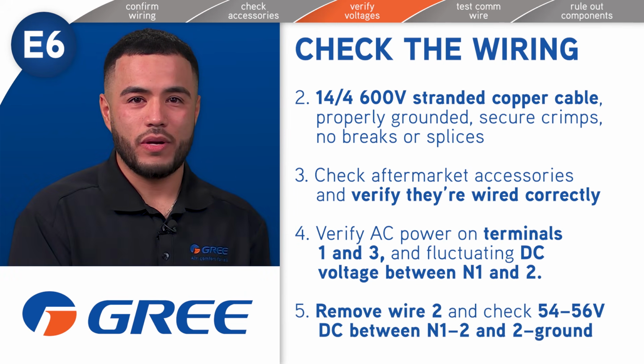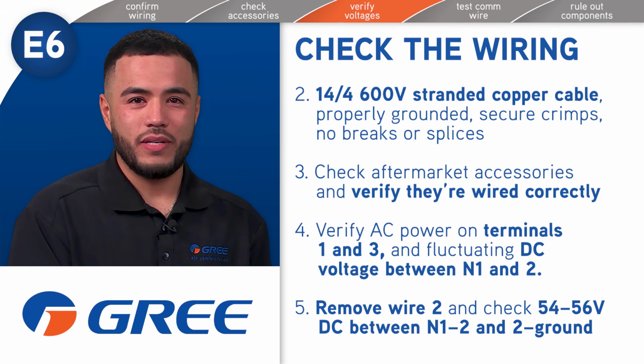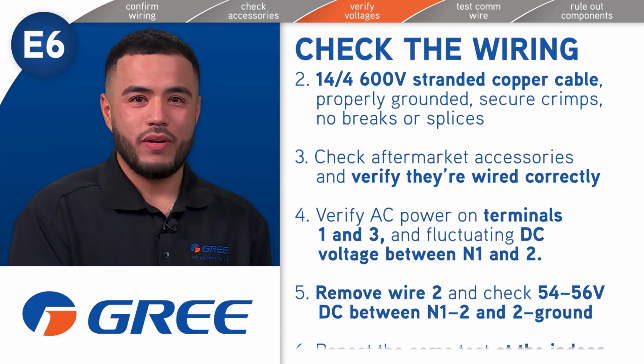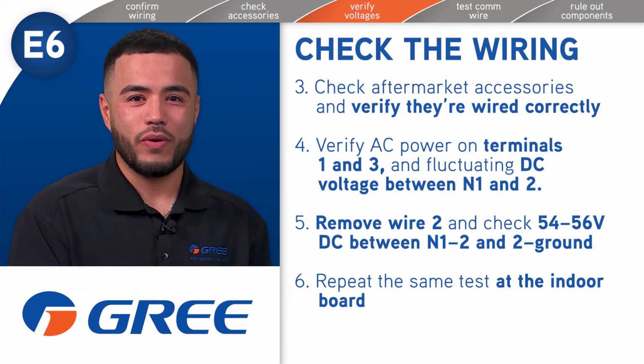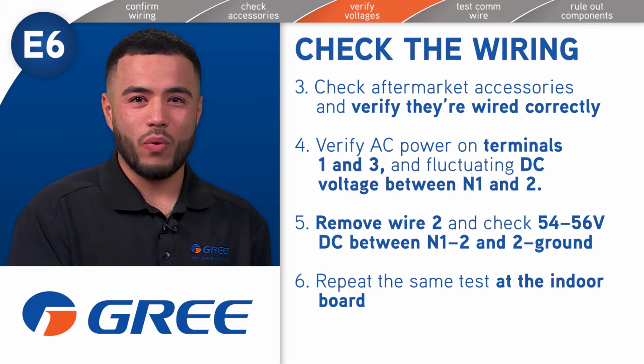At the outdoor board, remove wire number 2. Check for 54 to 56 volts DC from N1 to 2 and from 2 to ground. Repeat the same test at the indoor board. If voltage isn't stable in this range, a board, fuse, or component may be faulty.